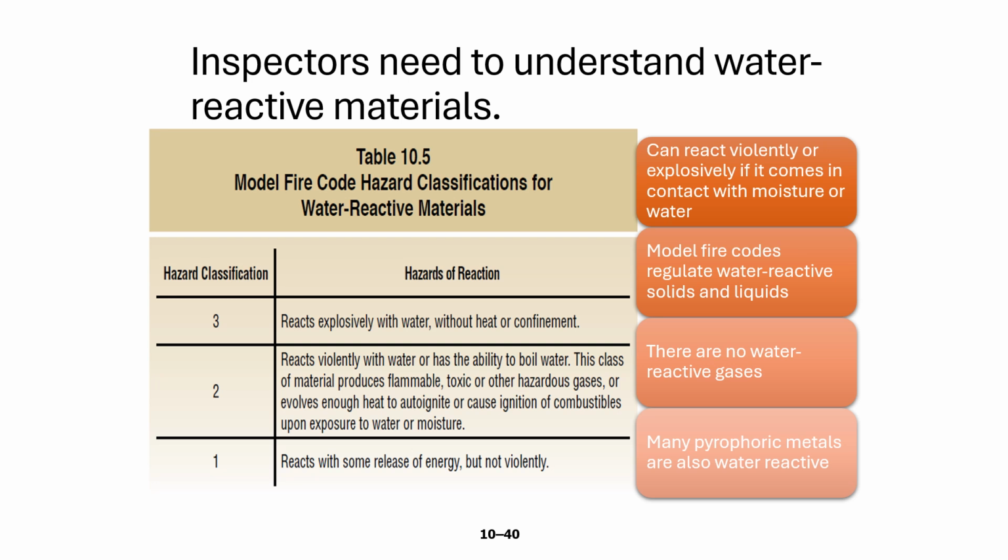All right, water reactive materials. We're almost through these categories, so we're getting close to the end of this objective. Water reactive materials can react violently or explosively when they come in contact with moisture or are improperly mixed with water. Our model codes regulate water reactive solids and liquids. They regulate how they should be protected, what the maximum allowable quantities are, and things like that. There are no water reactive gases. Many pyrophoric metals are also water reactive.